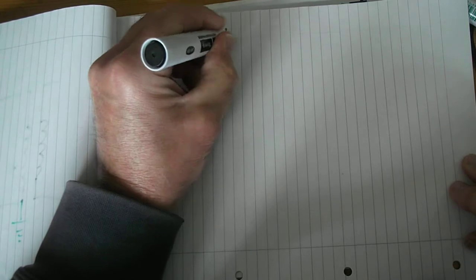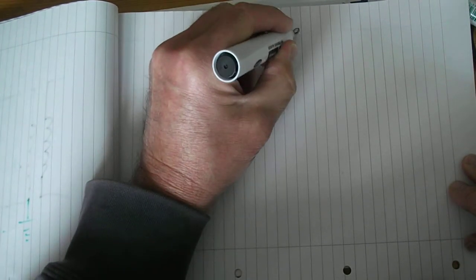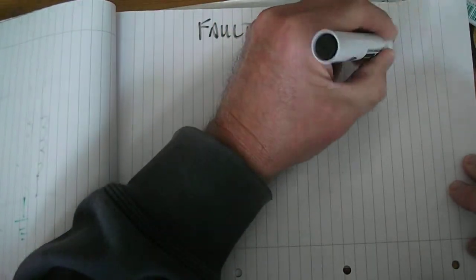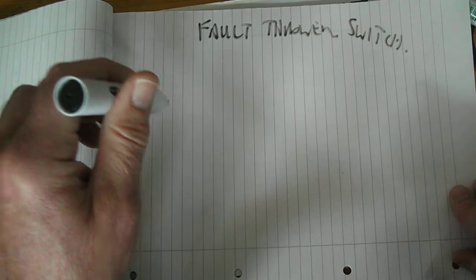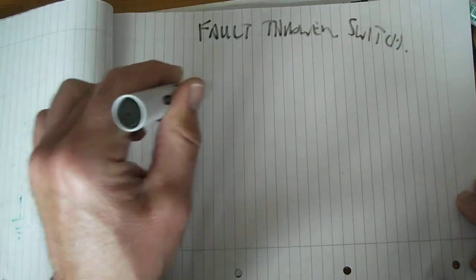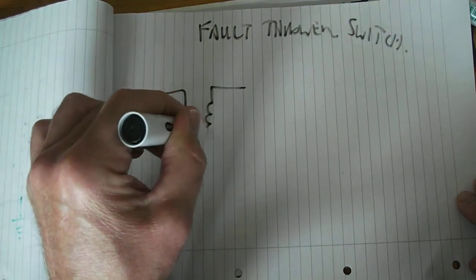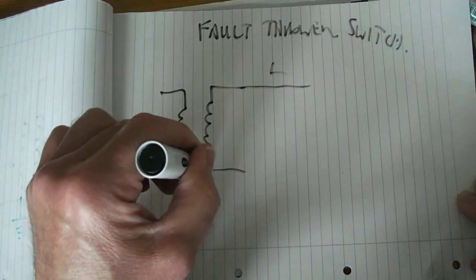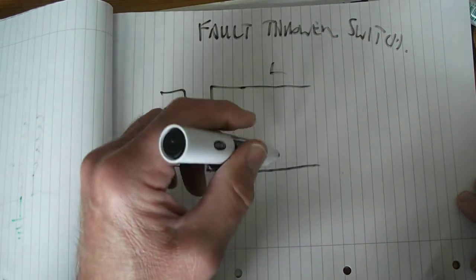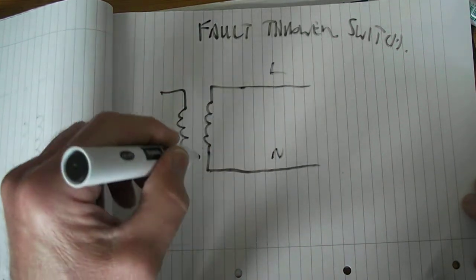Okay, here's the second clip, and you may come across the term a fault thrower switch. And there's our transformer again. And we've got live. I'm showing single phases here all the time to keep it simple, don't forget. Live and neutral, don't forget that's earthed at this end.